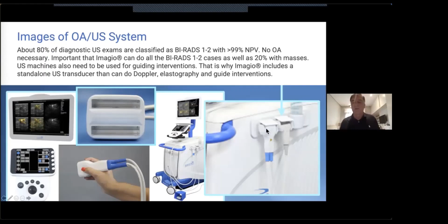Again, this is a bigger view of it, and you can see that this was a 38 millimeter transducer, but the newer transducer is going to be 50 millimeters, which is what we more typically use. Now, we fire ultrasound anywhere from 20 to 50 frames a second. We can only fire 10 laser pulses per second because we have to allow enough time between the pulses for the heat generated by the very brief low energy laser pulses to dissipate, to diffuse into the surrounding tissue, and also to be carried away by flowing blood. Most of what's getting heat is the blood, but as the blood flows, it's carrying the heat away. If we get a frame rate too high, then we can get heating.